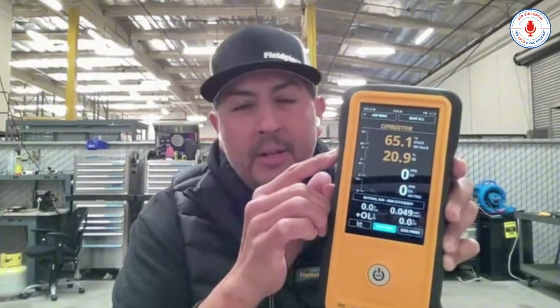Yeah. Fantastic. Okay, so now we're back on the job site and we are in our test port and we're sampling gases. We don't have to worry about water. Hooray, Fieldpiece. Now we can focus on what the measurements are actually telling us, right? And so, for diagnostic purposes, the main measurements you want to look at are your stack temperature, your oxygen percentage, and your carbon monoxide that is being generated in the flue, right? And so for a high efficiency furnace, you can expect a lower stack temperature, somewhere in the range of 100 to 130 degrees is kind of what you're looking for there. As far as your oxygen, you're looking somewhere between 6 and 9% is going to be the sweet spot.